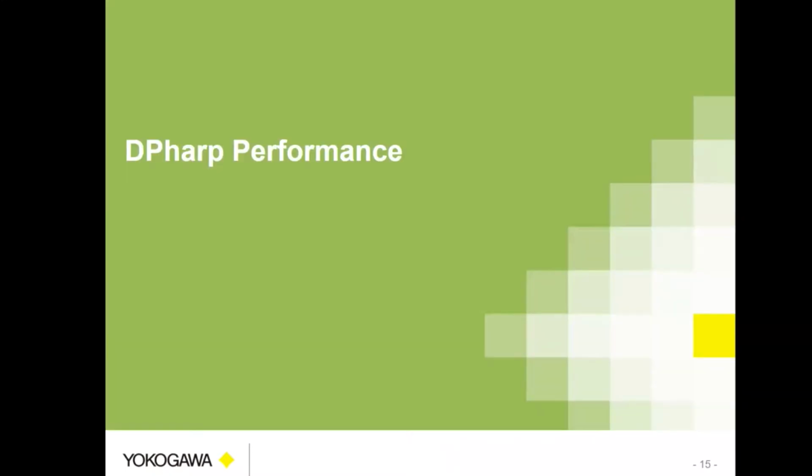So as far as performance, now before I show any type of low accuracies and things like that, it's important to understand what's really important here, because a lot of our manufacturers, they kind of battle each other, Rosemount or Endress+Hauser or Siemens or Honeywell or Yokogawa. They all try to have the best accuracy, right? That's on their spec. It's kind of a spec off between everyone. But what's really important, right, is the reliability and repeatability of the transmitter. If I say I got a very small accuracy that the customer can achieve, but I'm testing this under lab conditions, what good does that do if I'm out in West Texas or if I'm out in East Texas or somewhere where there's high temperature changes? It does me no good.